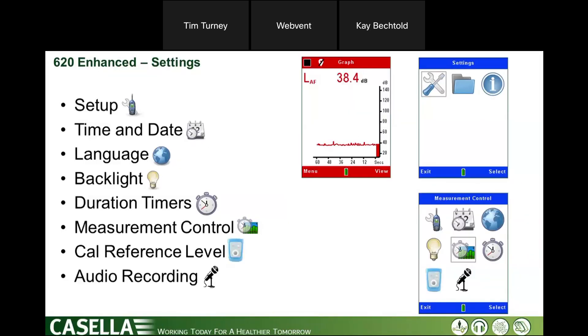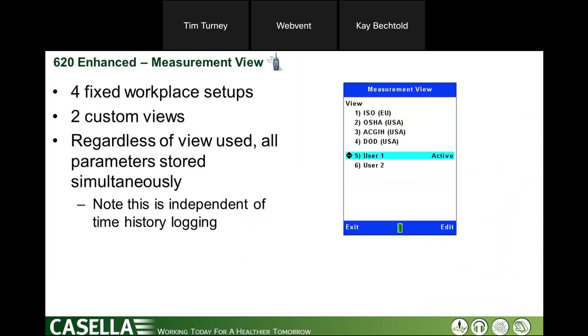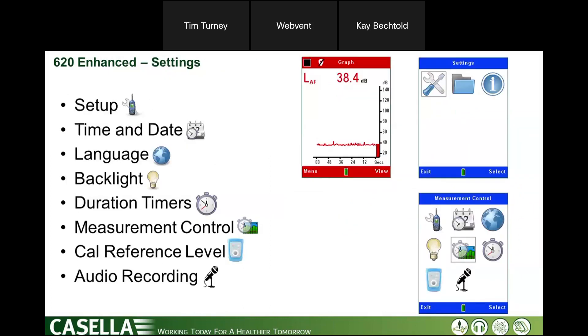In the settings, these are things you don't need to do on a regular basis. From the stop screen you go into settings, then into setup. These are fairly straightforward items indicated by icons: time and date, language, backlight, duration timers, and measurement control — where you set up time history storage, change your calibration reference level, and set up audio recording.